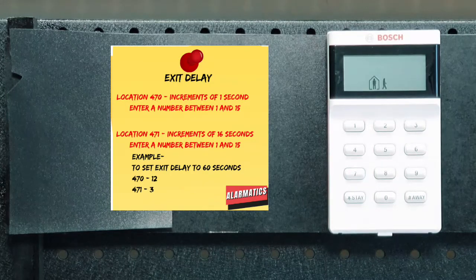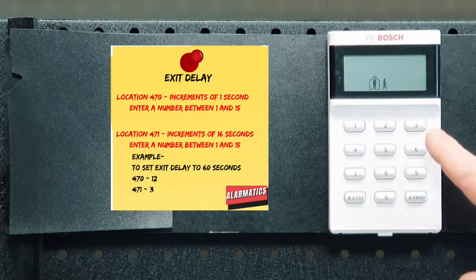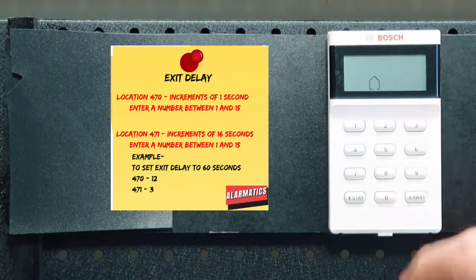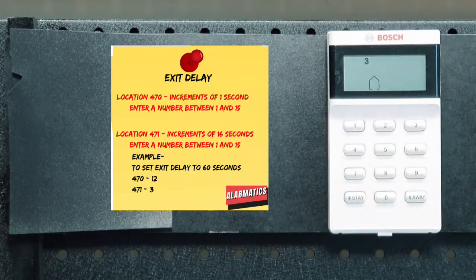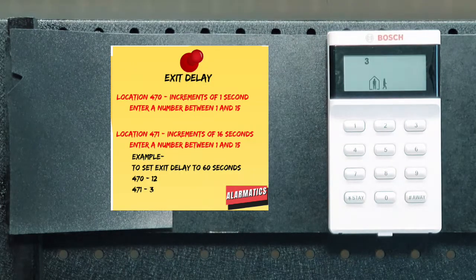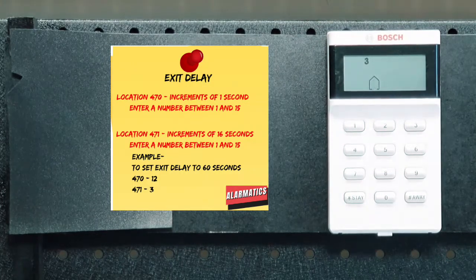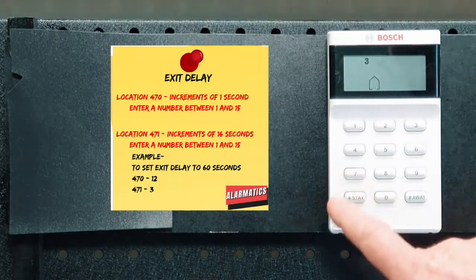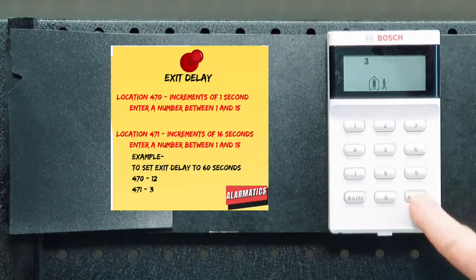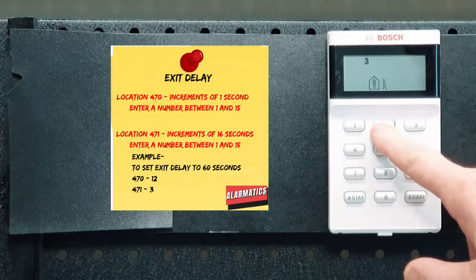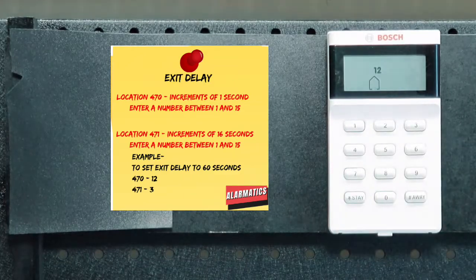In this example, as I said, I'll make this 60 seconds. So I want 3 blocks of 16. So I enter 3 and save it. So 3 16s are 48. Is that right? 48 seconds. Yep, 48 seconds. Okay, and then I go back to 470. And if I put a 12 in there, the 48 plus 12 gives me 60 seconds.